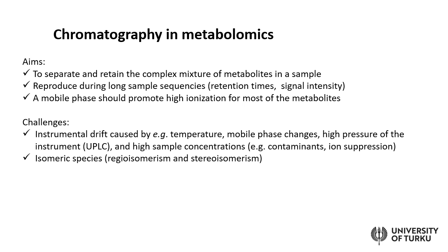And of course here then there are many analytical challenges as in any analytical chemistry method, and when it comes to chromatography, those that we typically encounter are first of all the instrumental drift, so that no matter how you have adjusted your conditions, still you can see that the signal is not reproducible, so that there is a drift that is caused by, for example, the temperature in the room changing, the mobile phase composition not remaining the same, the pressure giving a lot of demand for the instrument, and also then there might be something inherent in your sample that can be causing drifts, and also then gradually the more samples you run, the more dirty your column gets.